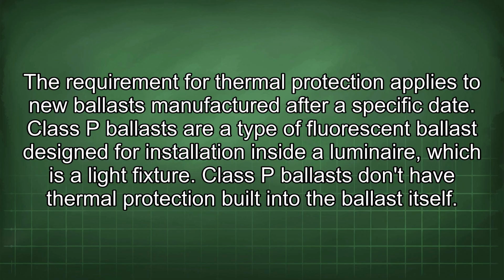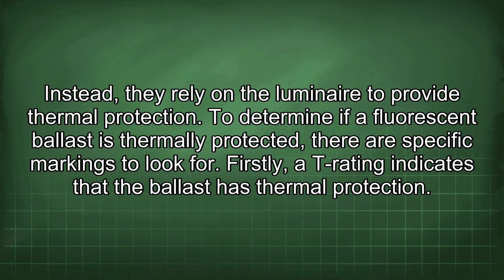Class P ballasts are a type of fluorescent ballast designed for installation inside a luminaire, which is a light fixture. Class P ballasts don't have thermal protection built into the ballast itself. Instead, they rely on the luminaire to provide thermal protection.